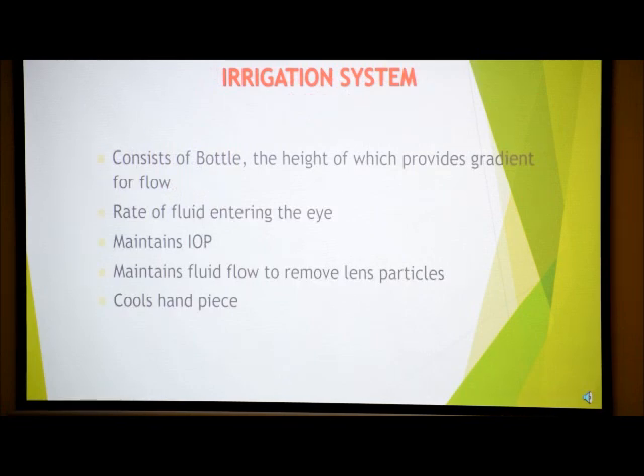Irrigation system consists of a bottle, and the whole purpose of irrigation is to maintain the anterior chamber, maintain the cornea, maintain the iris diaphragm, and maintain the posterior capsular position. It maintains IOP, and the thumb rule is the standard bottle height should usually be 60 to 65 centimeters above the patient's eye level. And how does that convert to intraocular pressure? This simple rule: 15 centimeters of bottle height equals 11 mm of mercury in intraocular pressure.